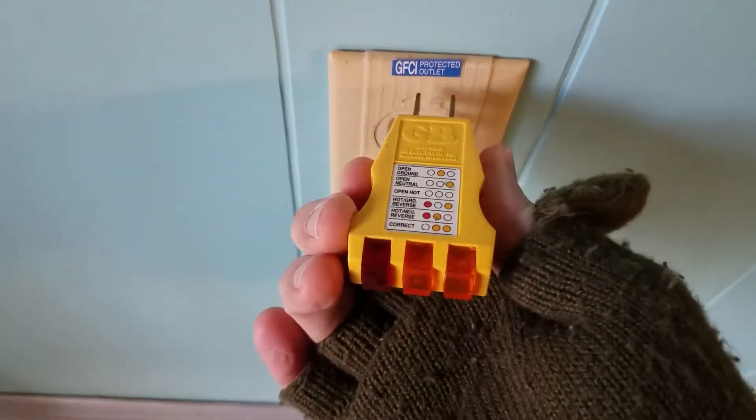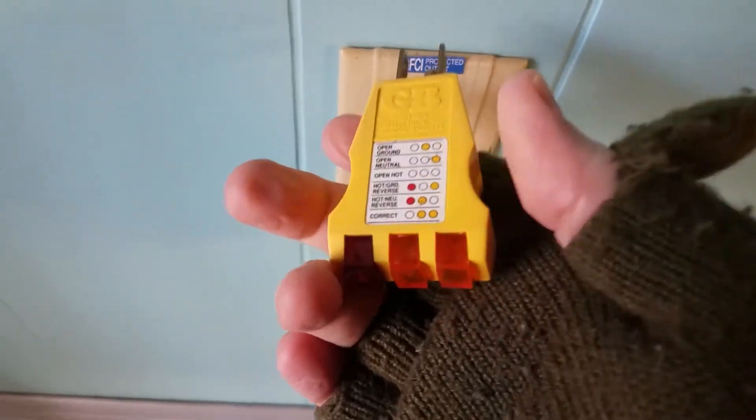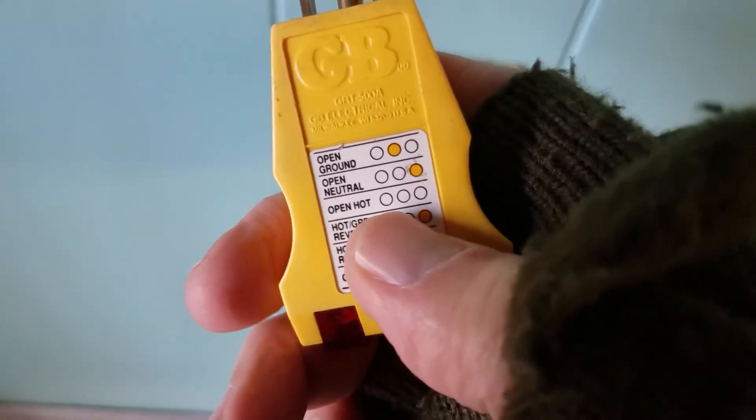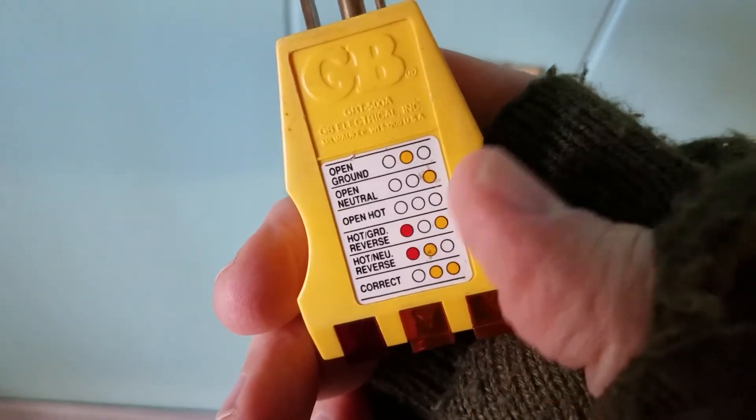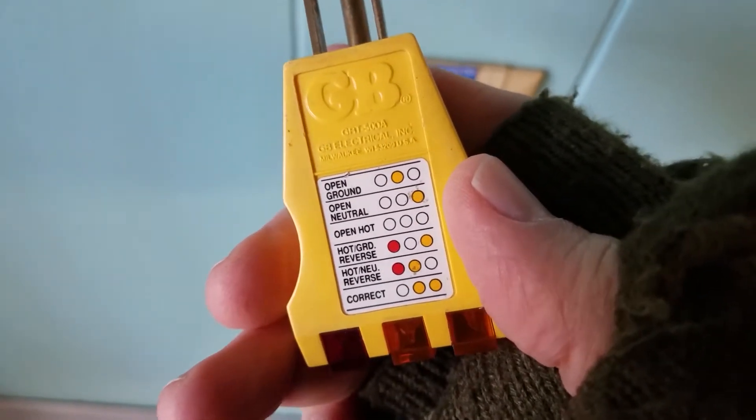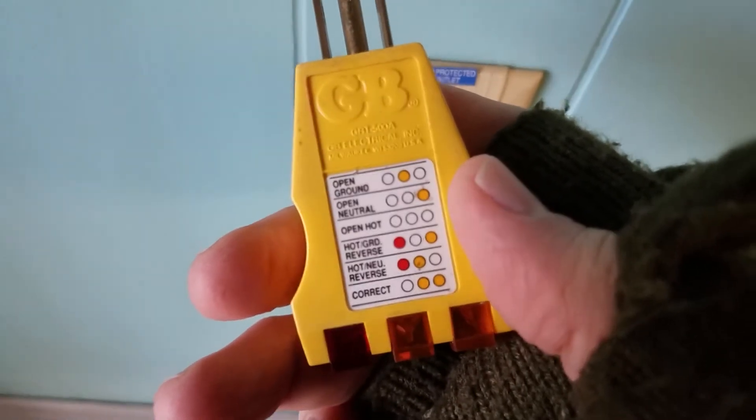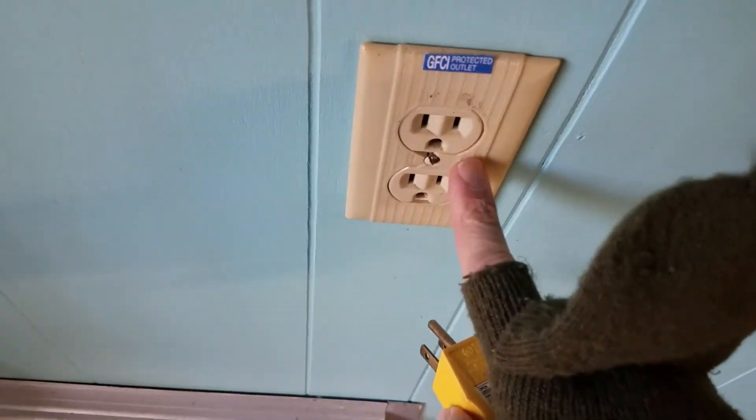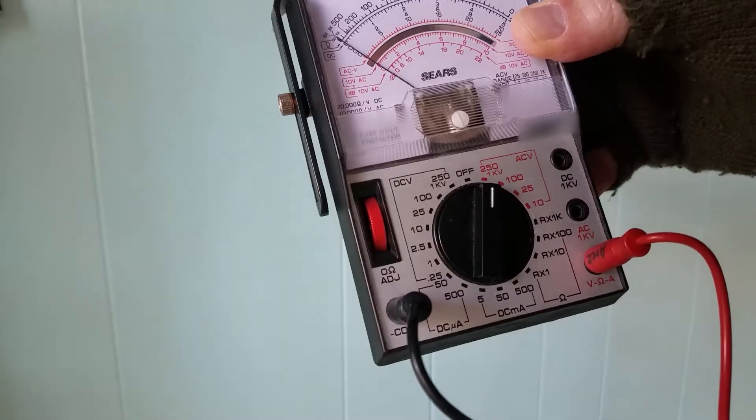Well no, because if you look here it says that if all the lamps are off it could also be an open hot, which could be a dangerous situation because you could electrically shock yourself. So this is not the tool to verify that this circuit is off.